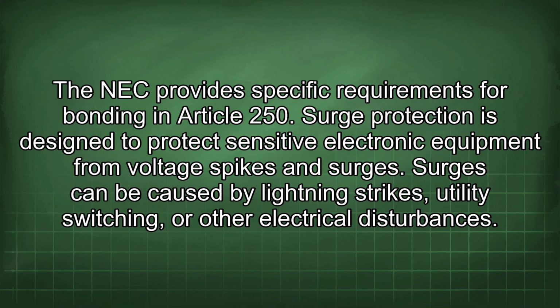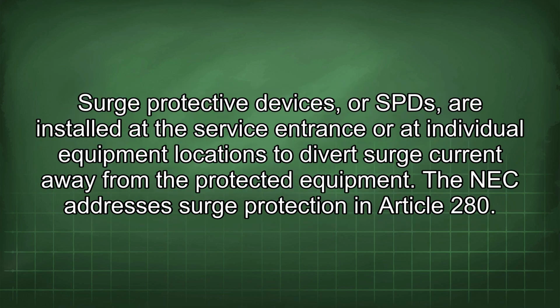Surge protection is designed to protect sensitive electronic equipment from voltage spikes and surges. Surges can be caused by lightning strikes, utility switching, or other electrical disturbances. Surge protective devices, or SPDs, are installed at the service entrance or at individual equipment locations to divert surge current away from the protected equipment. The NEC addresses surge protection in Article 280.